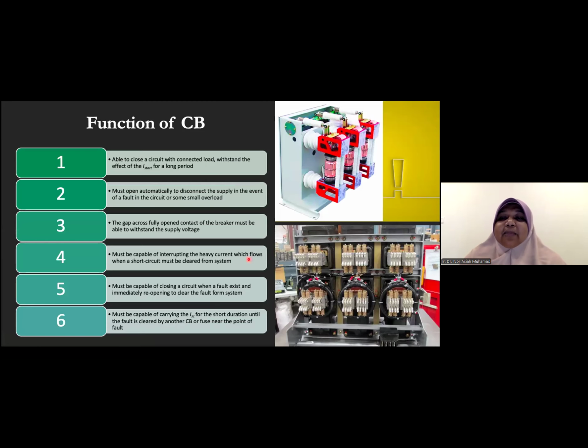So this is a picture of a vacuum circuit breaker. Inside this are two separated conductors, two terminals, electrodes, positive and negative. When there is a fault, the terminals will be separated. The circuit will be disconnected. Where we put it here, so this is the main, then we lock it into here. So this is the main connecting to the load, to the system.